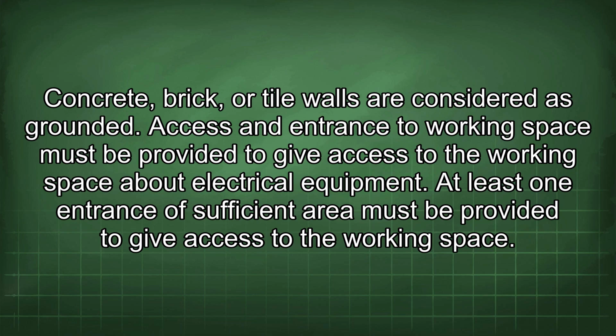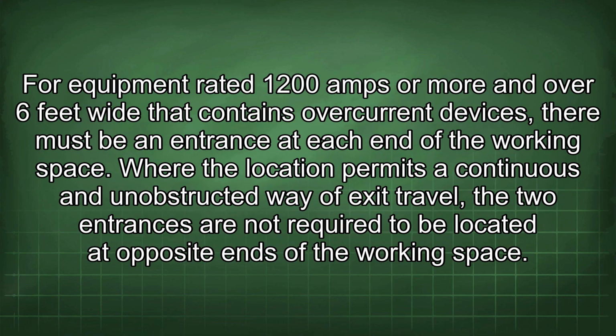Access and entrance to working space must be provided to give access to the working space about electrical equipment. At least one entrance of sufficient area must be provided to give access to the working space. For equipment rated 1200 amps or more and over 6 feet wide that contains overcurrent devices, there must be an entrance at each end of the working space. Where the location permits a continuous and unobstructed way of exit travel, the two entrances are not required to be located at opposite ends of the working space.